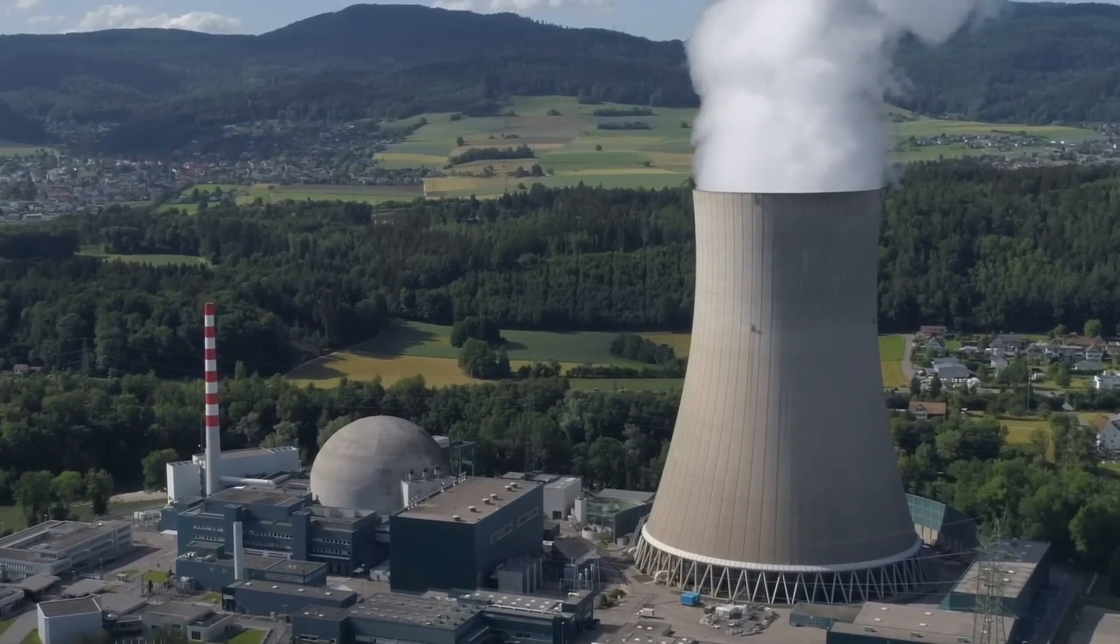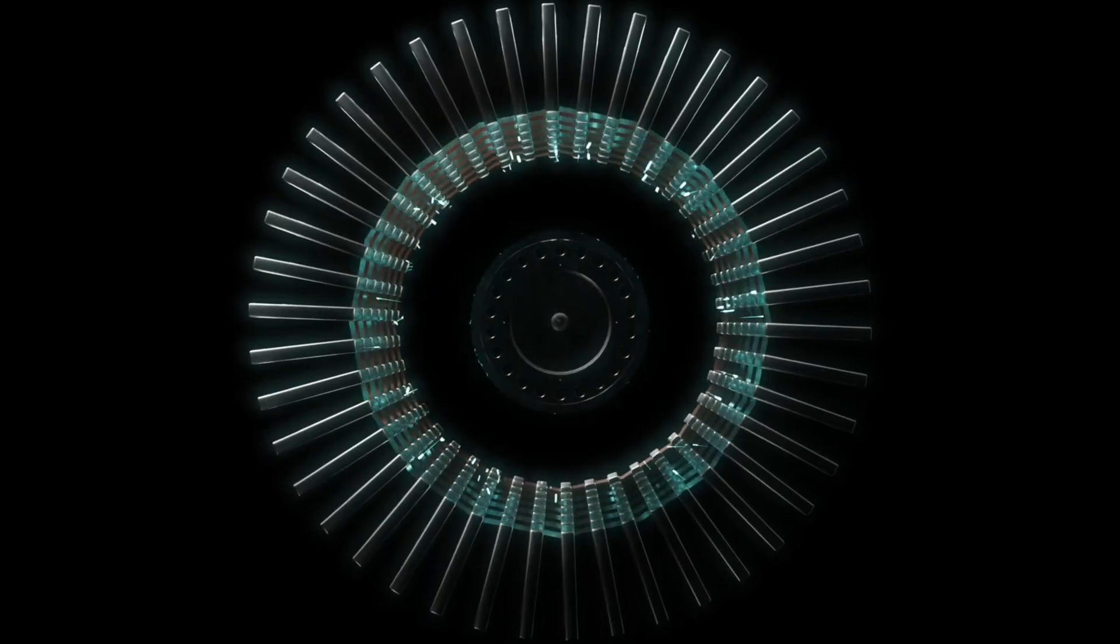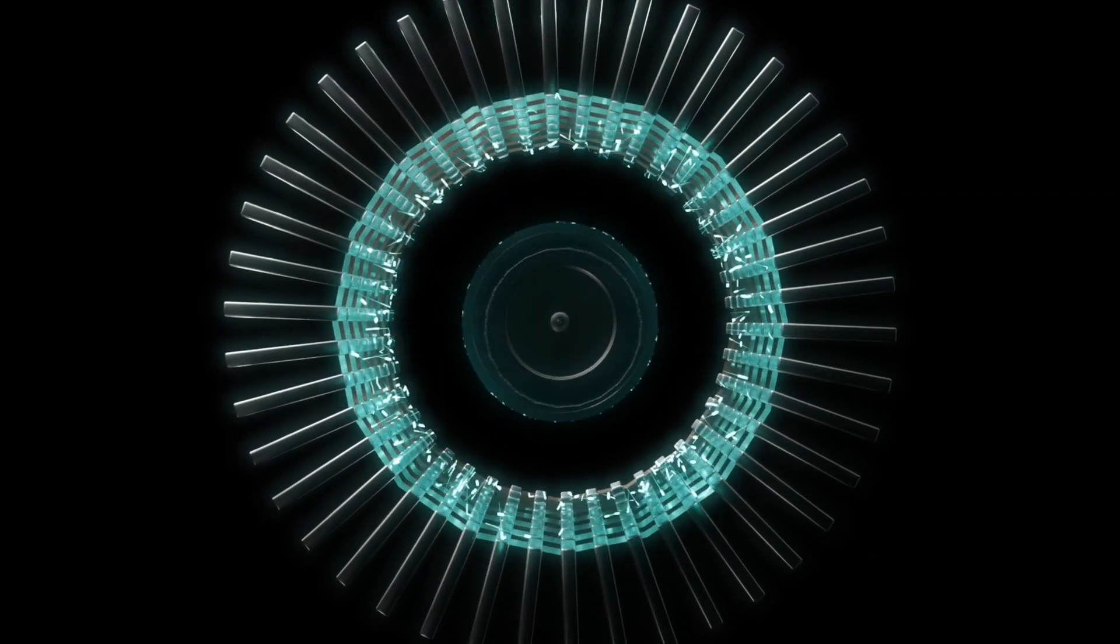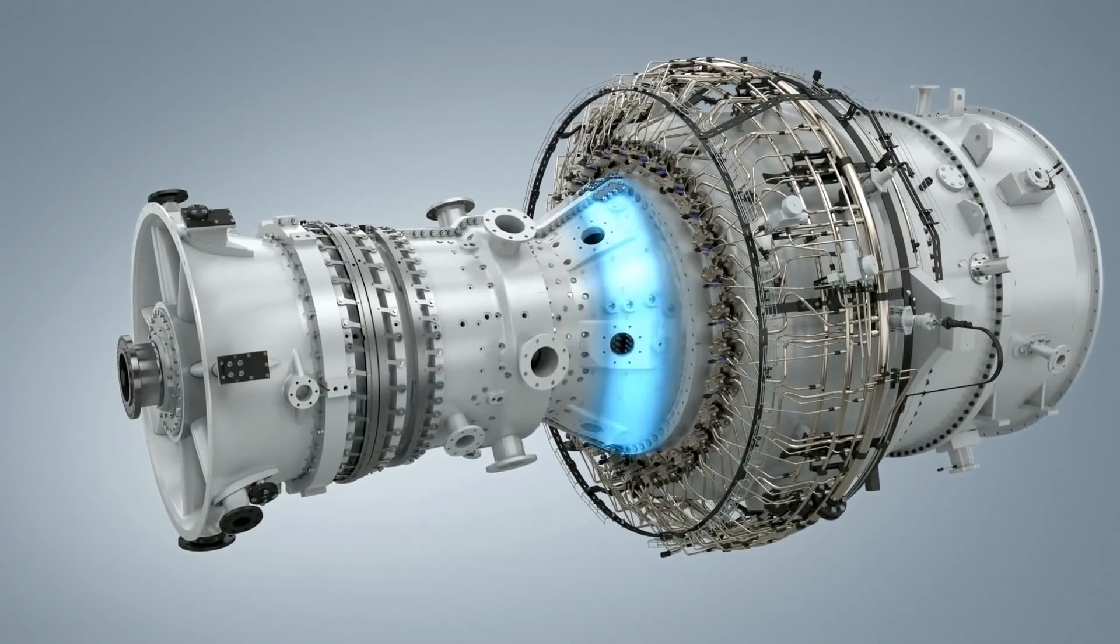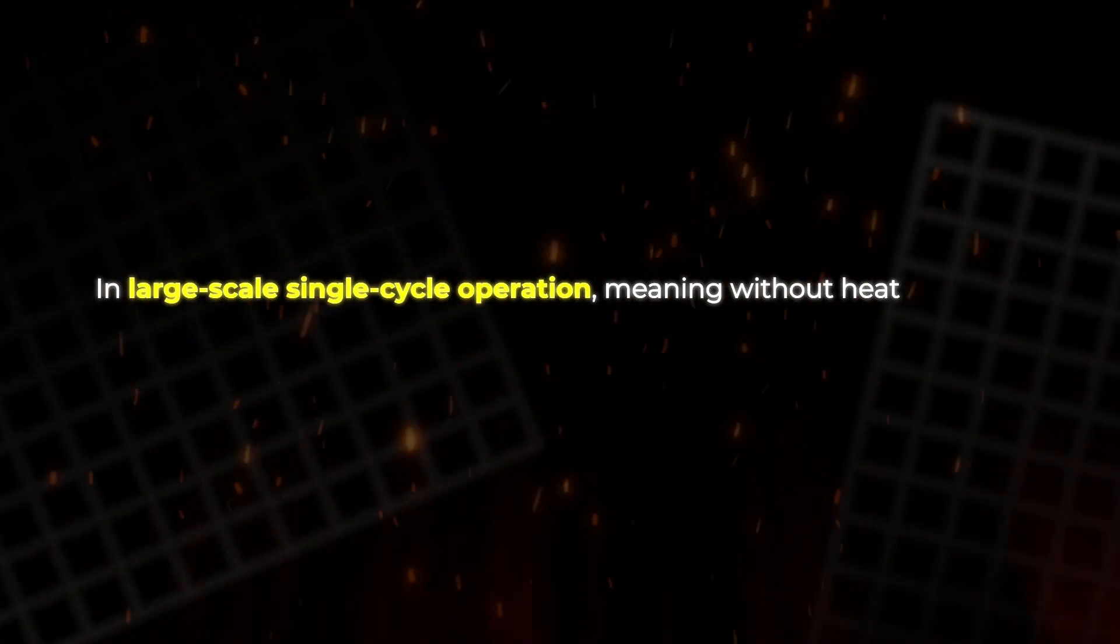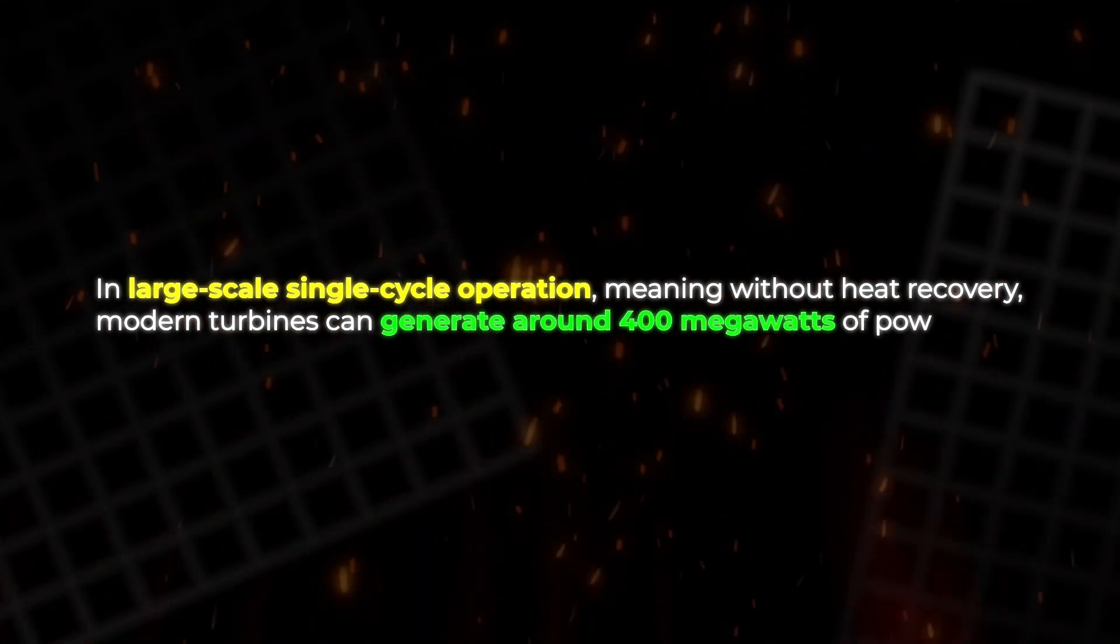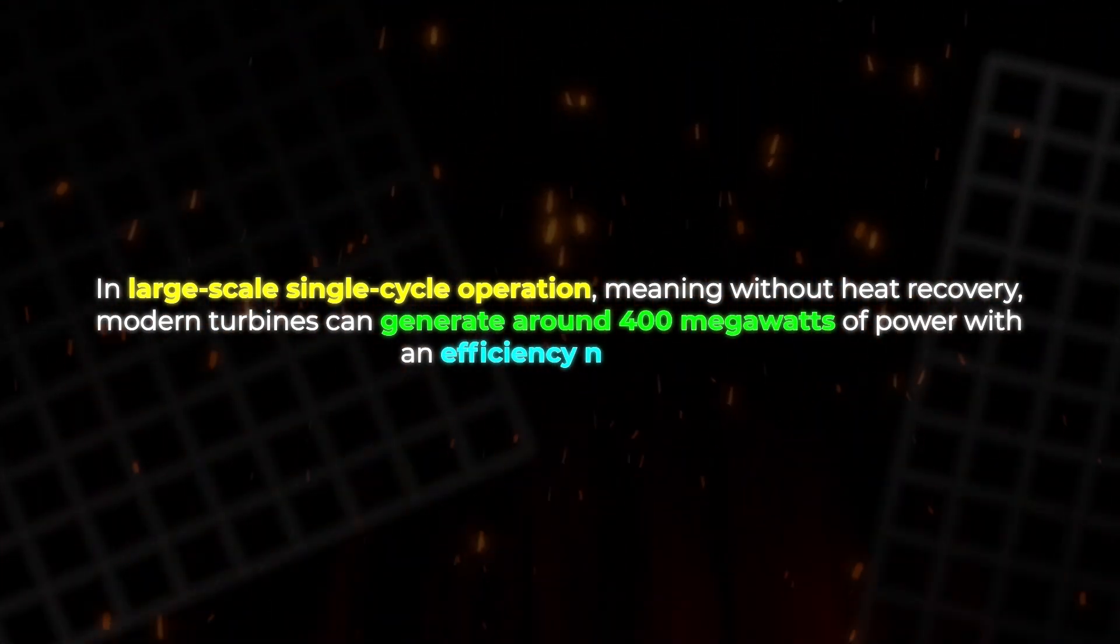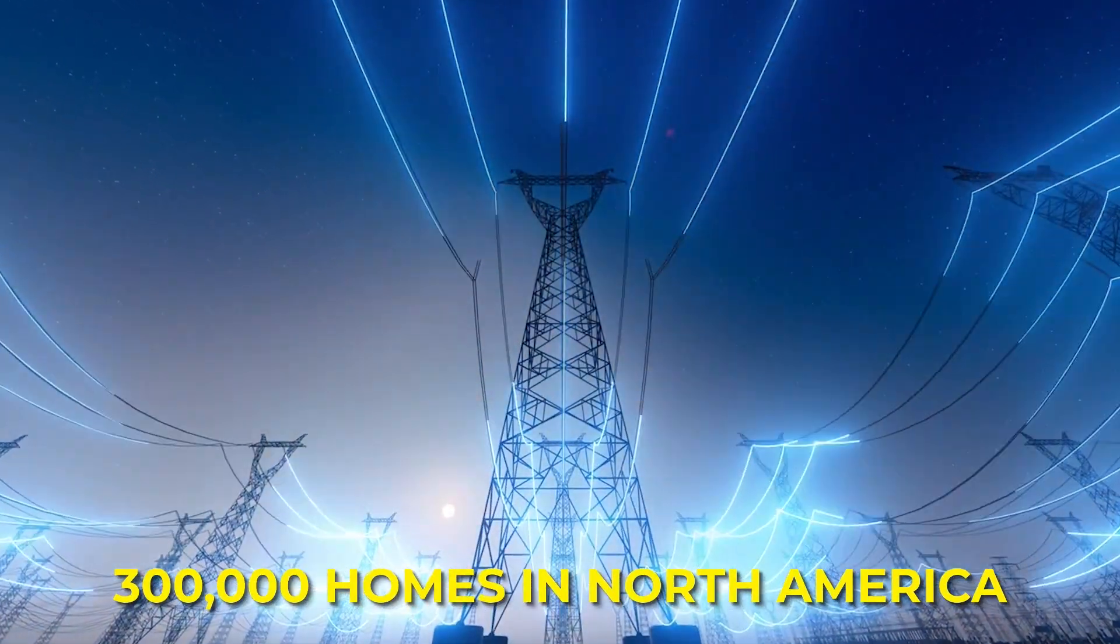Among fossil fuels, natural gas stands out for its high energy density. Aside from hydrogen, it contains more energy per unit of mass than almost any other commonly available fuel. That's one reason gas turbines are so powerful and efficient. In large-scale single-cycle operation, meaning without heat recovery, modern turbines can generate around 400 megawatts of power with an efficiency near 40%. That's enough to supply electricity for roughly 300,000 average homes in North America.